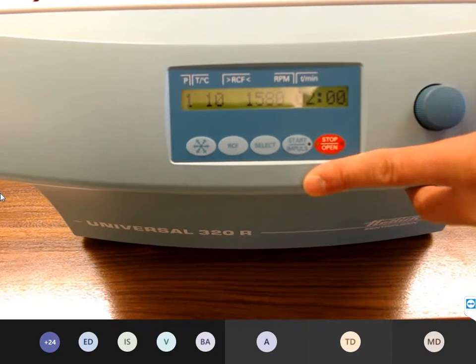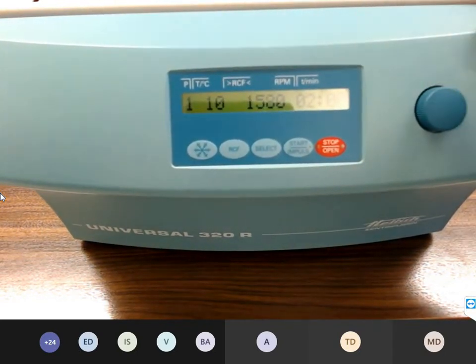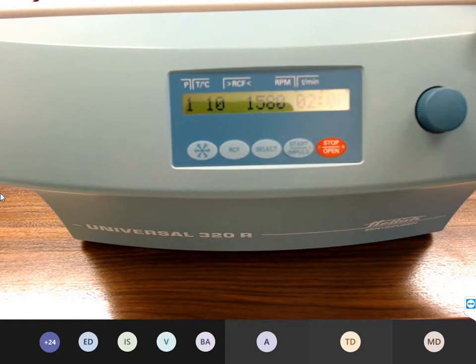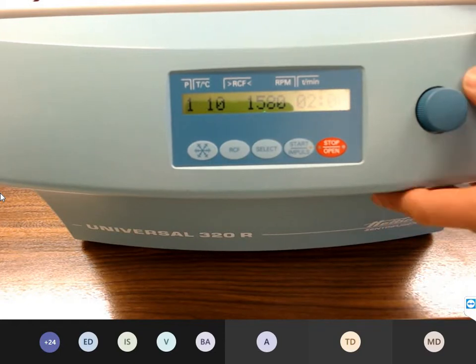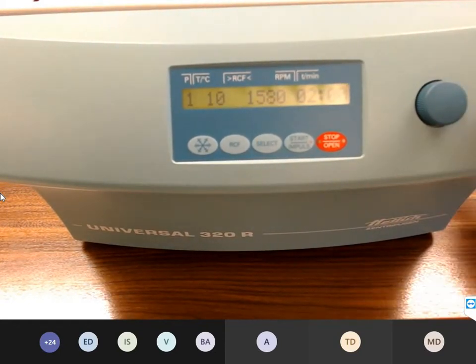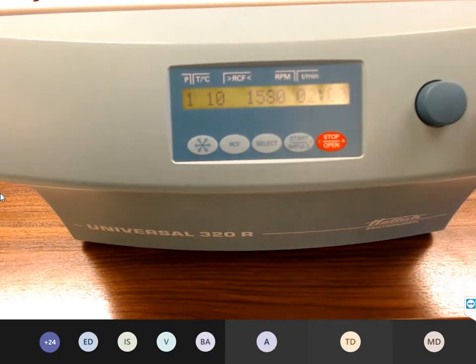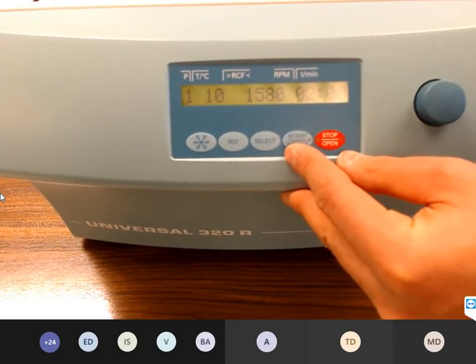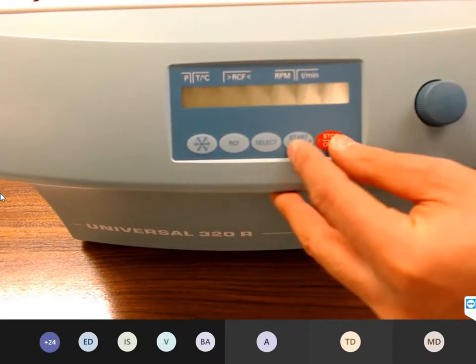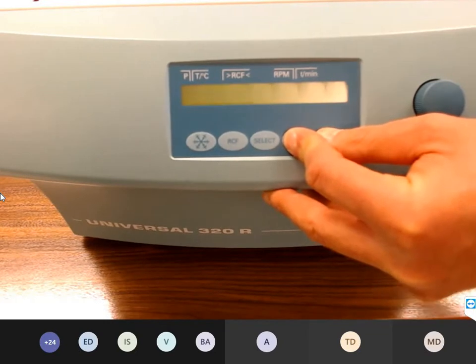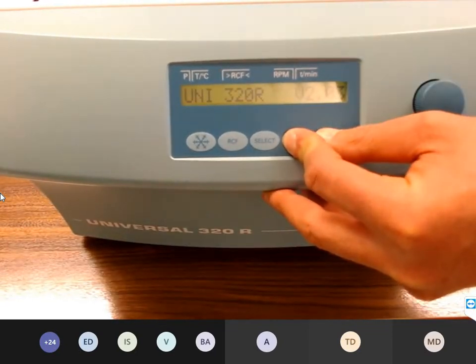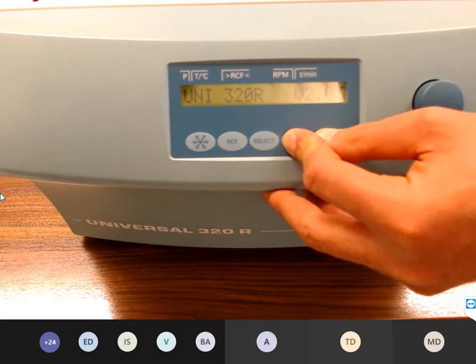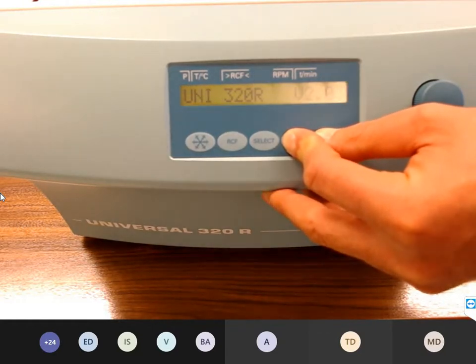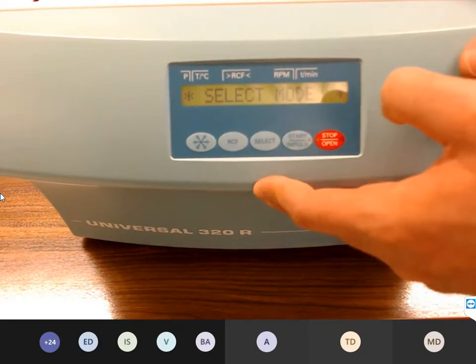The access to the function test for the universal and Micro 220R is a little bit different. We don't need to remove 2 jumpers for the access to the service mode. We only have to switch off the device, press the start and stop key, switch on, and press these 2 keys for 16 seconds. Very important. Hold these 2 keys. Now we are in the select menu.